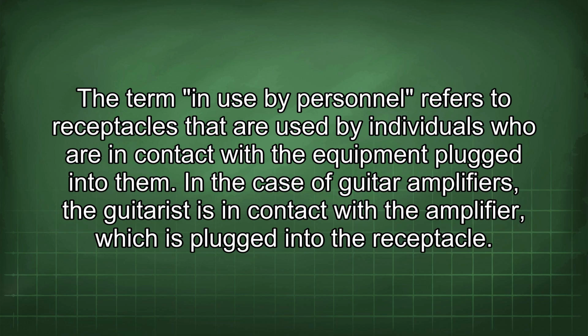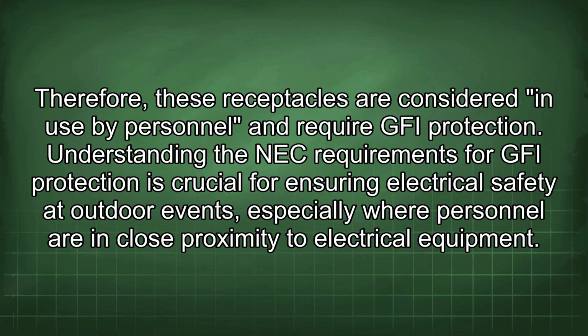The term "in use by personnel" refers to receptacles that are used by individuals who are in contact with the equipment plugged into them. In the case of guitar amplifiers, the guitarist is in contact with the amplifier, which is plugged into the receptacle. Therefore, these receptacles are considered in use by personnel and require GFI protection. Understanding the NEC requirements for GFI protection is crucial for ensuring electrical safety at outdoor events, especially where personnel are in close proximity to electrical equipment.